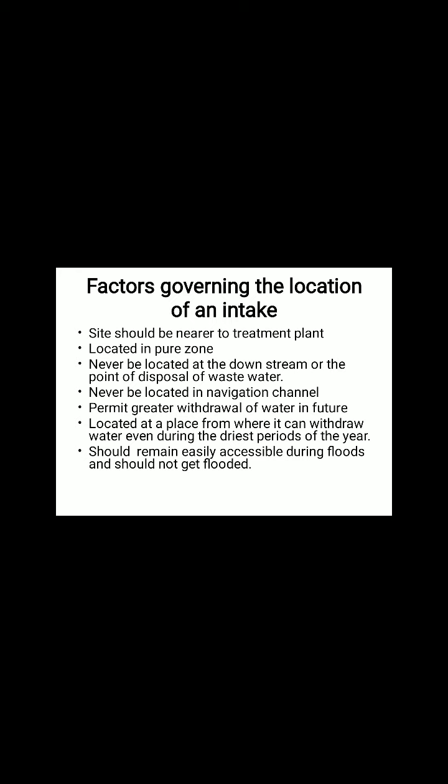Third, it should not be located at the downstream or the point of disposal of the wastewater. If it is in the downstream, it will unnecessarily get polluted. Next, it should not be located in the navigational channel, as otherwise there are chances of the intake water getting polluted due to the discharge of waste from the ships and the boats.